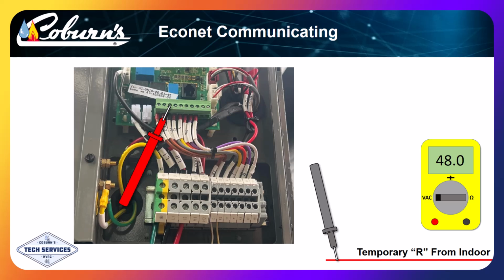If 48 volts is found, we need to power down the equipment and swap the L1 and L2 shown here. Once we have verified a 0 volts reading across our 2 R's, we are finished with verifying the transformers are phased correctly and can proceed with our startup and commissioning.